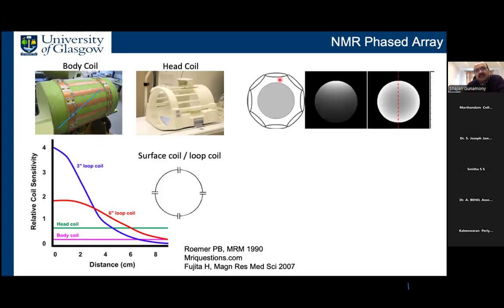So here you can see this is a phantom in the middle, and you have 8 coils around this phantom. So let's say you have only one of these coils here. Then you produce an image like this where the signal is very strong next to the coil, and it falls off when you go away from the coil, as you see in this plot here. But if you now have 8 of these coils surrounding this phantom, then you spread the sensitivity, or you carry over the advantage of one coil to the whole volume. And then you get an image with a much higher sensitivity.